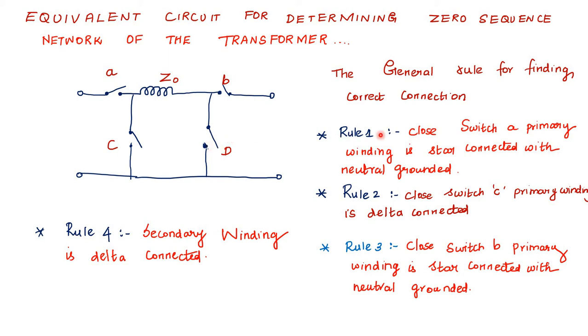The rules are as follows. Rule number one: close switch A when the primary winding is star connected with neutral grounded. Rule number two: close switch C when the primary winding is delta connected. Rule number three: close switch B when the primary winding is star connected with neutral grounded. Rule number four: close switch D when the secondary winding is delta connected.